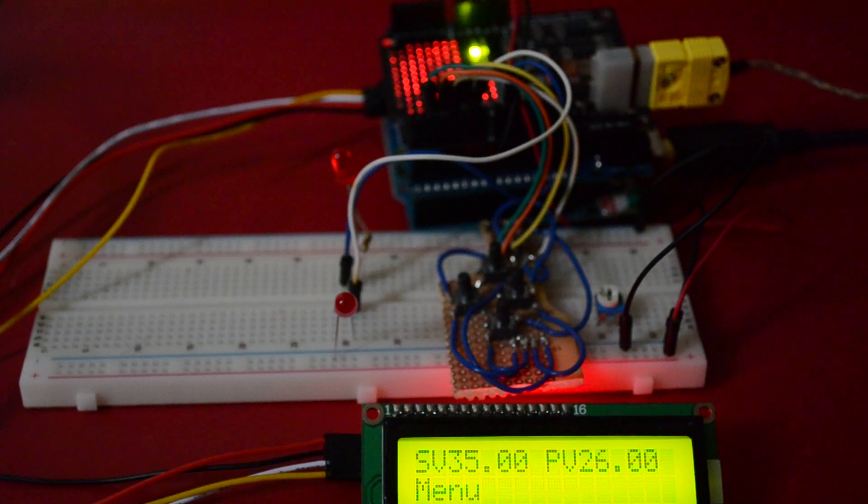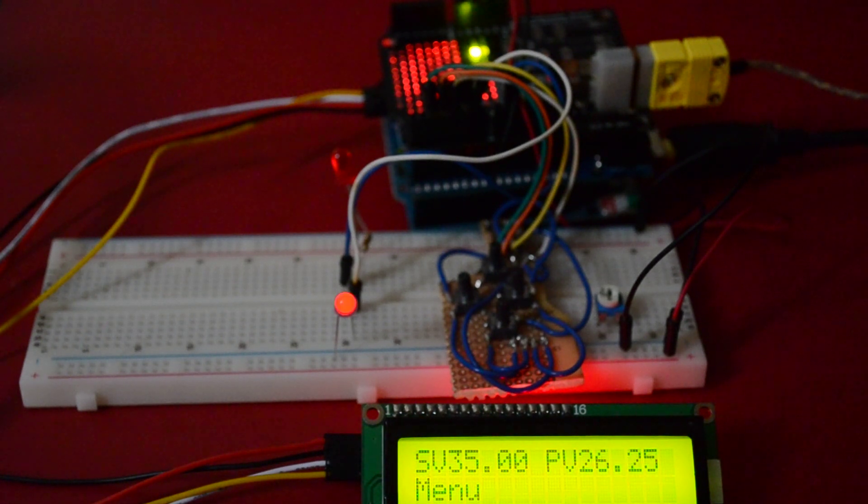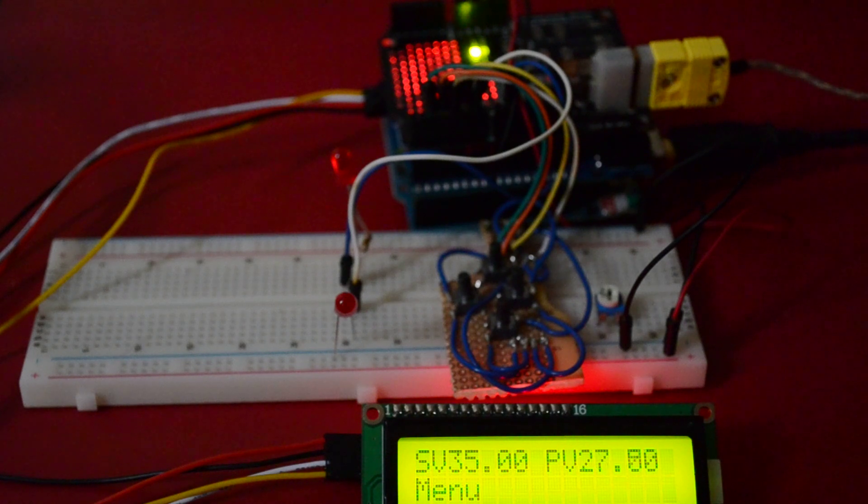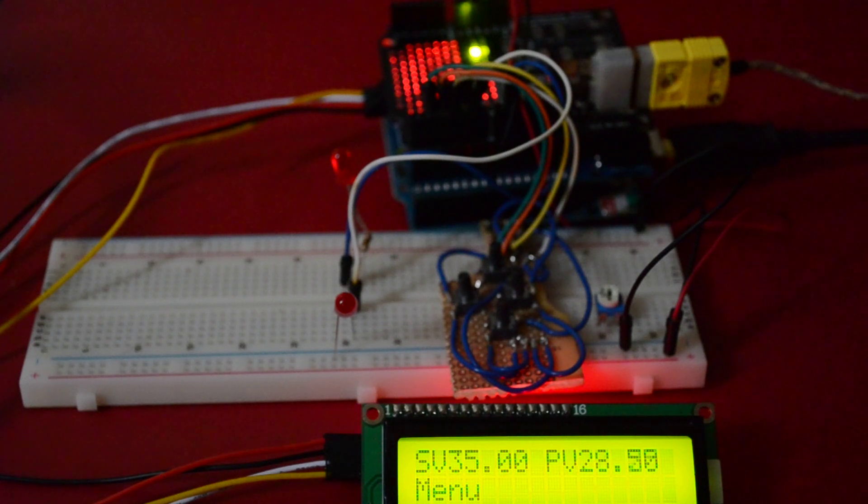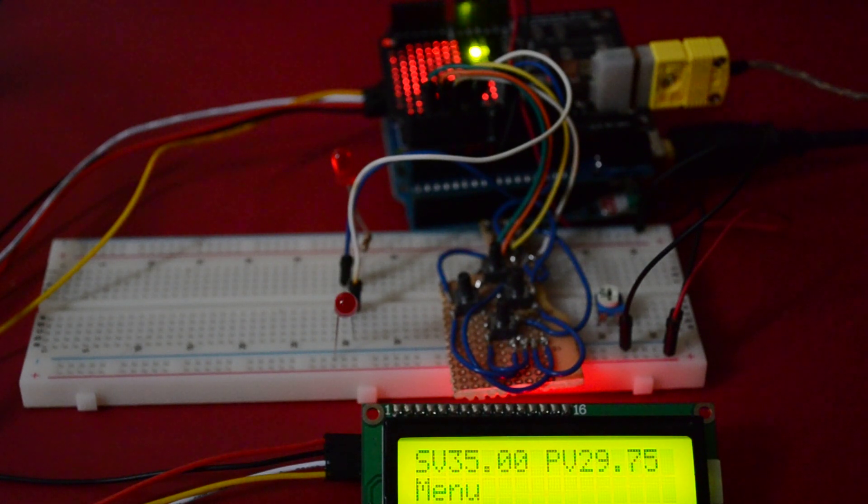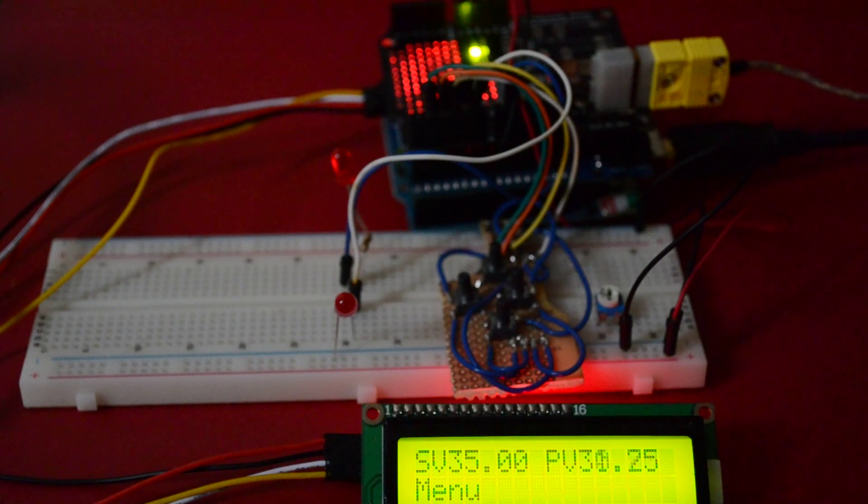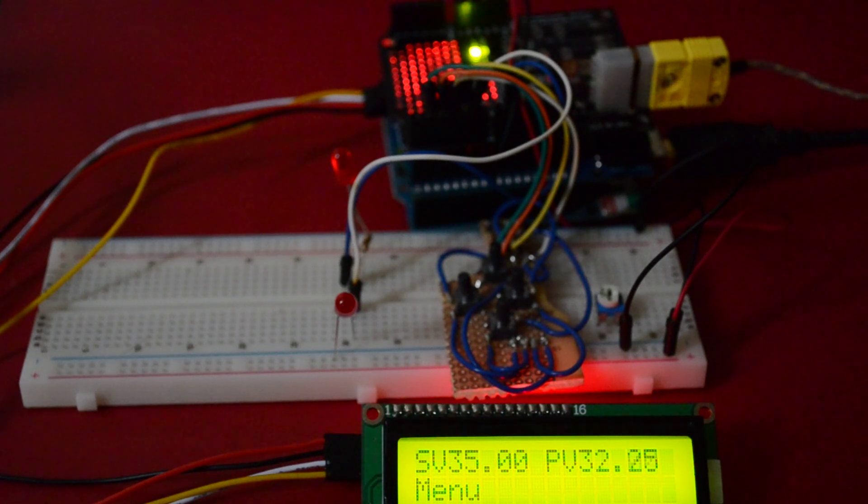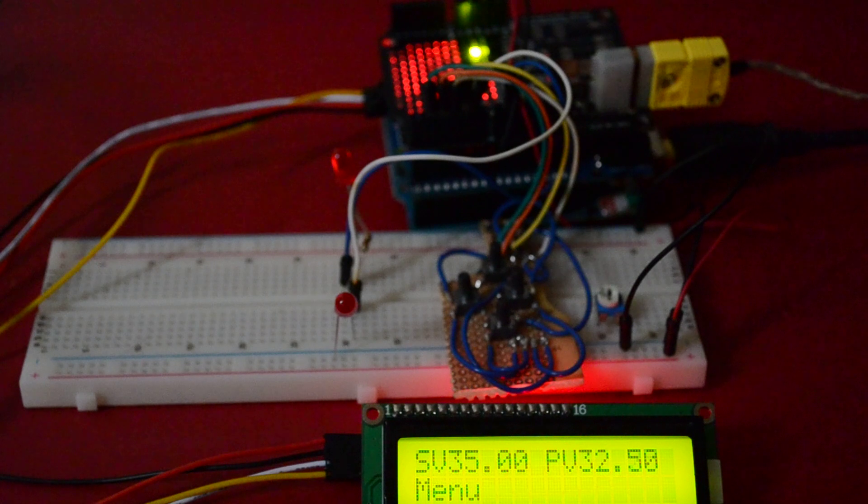So as the temperature rises, you can see the process value is starting to increase there, 27, 28, 29 degrees. It's approaching the 35, the pulses are getting shorter and shorter.